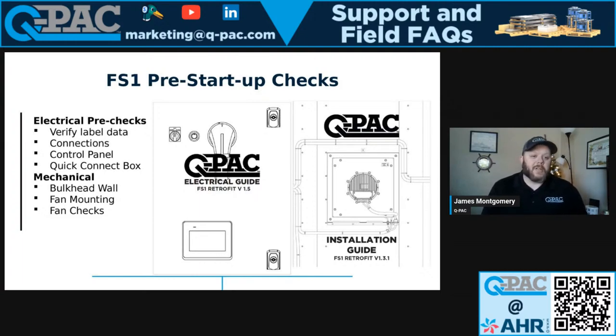So I start with the electrical pre-checks. Obviously, everything is de-energized. I'm going to make sure I obey all local safety, lockout, tagout requirements to make sure that everything is safe to work on, do my initial voltage verification, things like that. But I start with doing a voltage verification.